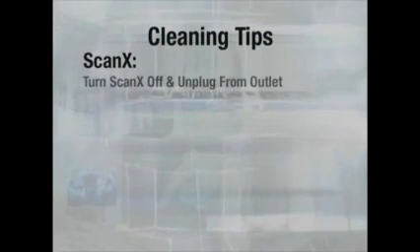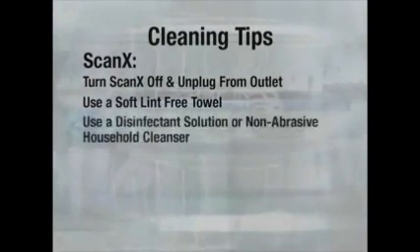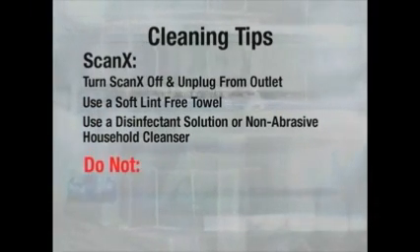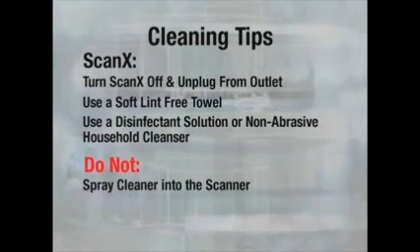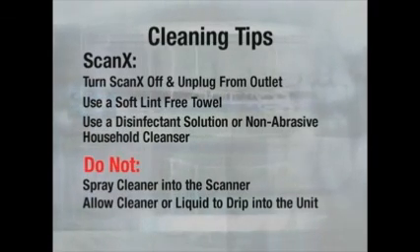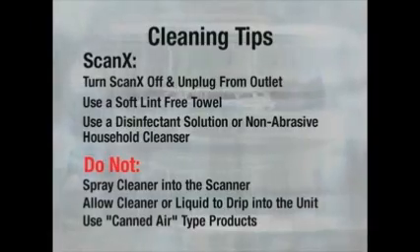Just a few more thoughts. One of the greatest benefits to ScanX is that it's designed to be maintenance-free for many years. If you want to clean your ScanX, first turn it off and unplug it from the outlet. Use a soft, lint-free towel and a disinfectant solution or a non-abrasive household cleaner. Protect your ScanX by making sure you never spray cleaner directly onto the scanner. Make sure no cleaner or liquid drips into the unit and canned air-type products should not be used because they will blow dust into the ScanX. Let the unit air-dry before plugging it back in.